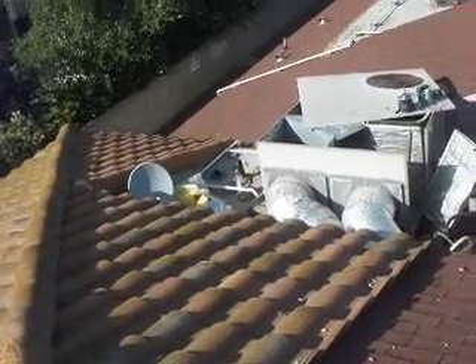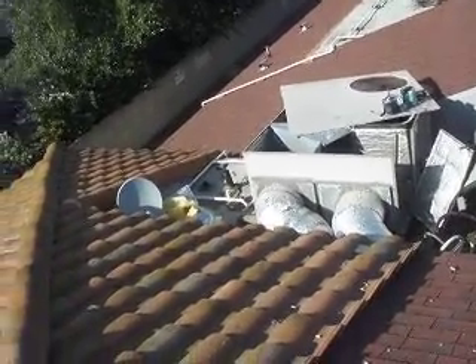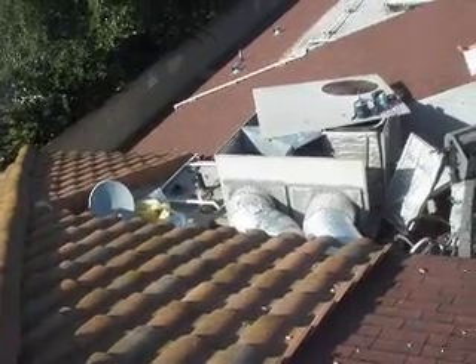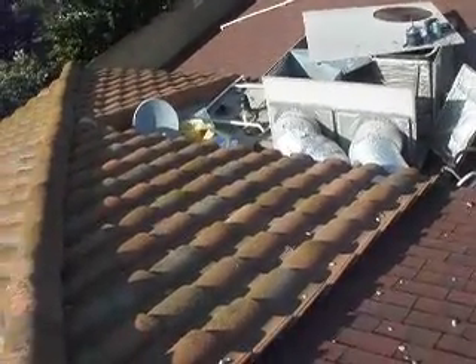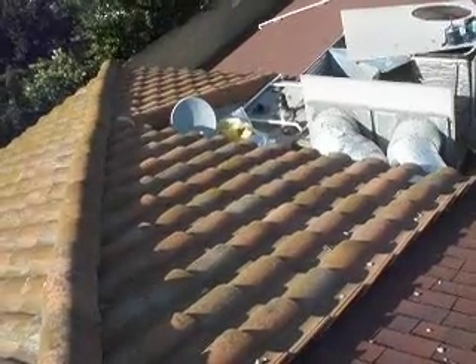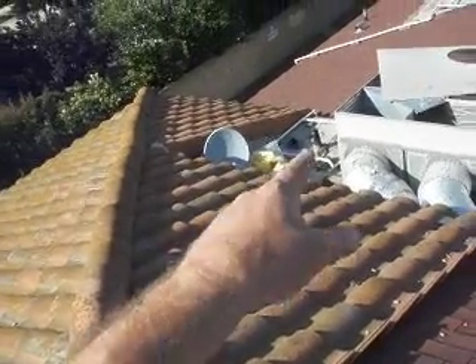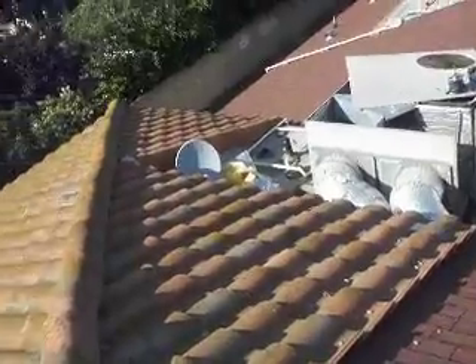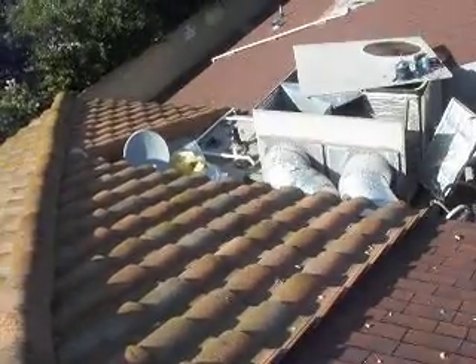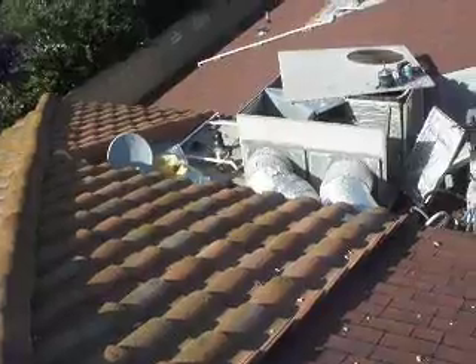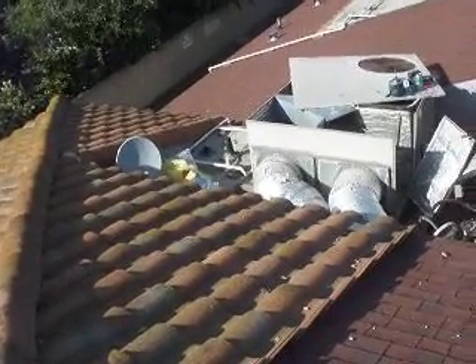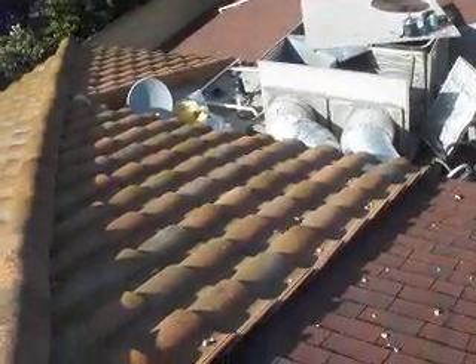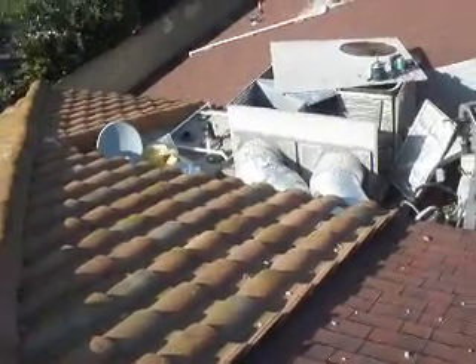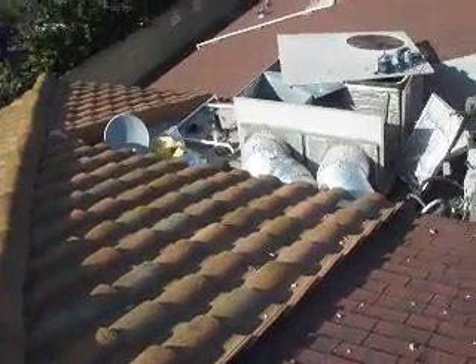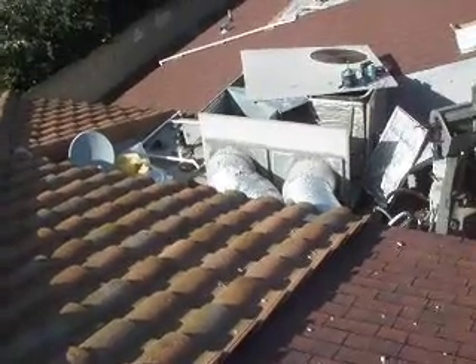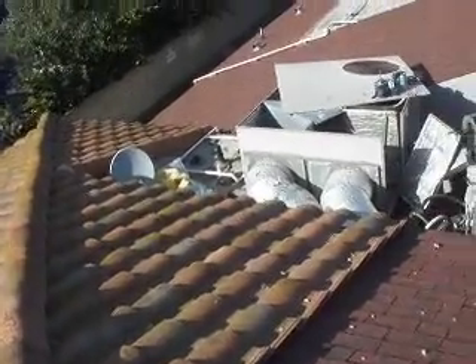Most of the big problem with this shopping center is just the ducting up inside. It all needs to be redone and done properly. The ducting that comes from the unit up into the roof, a lot of it's undersized because there used to be smaller units here. So when people upgrade to bigger units, due to more heat load in the business, they get choked off and don't have proper airflow, which causes equipment problems, and of course the efficiency goes right out the window.